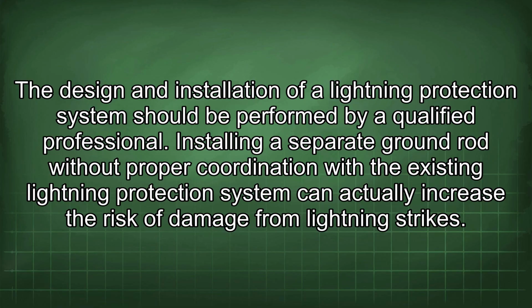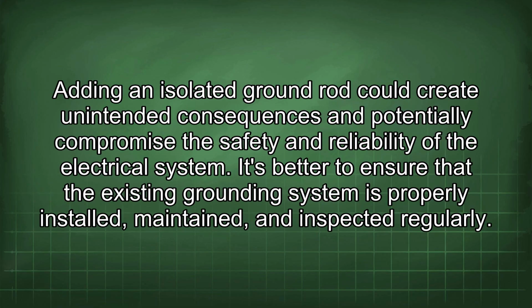Installing a separate ground rod without proper coordination with the existing lightning protection system can actually increase the risk of damage from lightning strikes. Adding an isolated ground rod could create unintended consequences and potentially compromise the safety and reliability of the electrical system. It's better to ensure that the existing grounding system is properly installed, maintained, and inspected regularly.